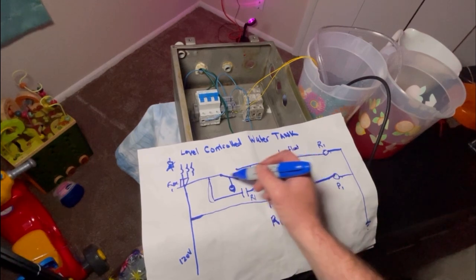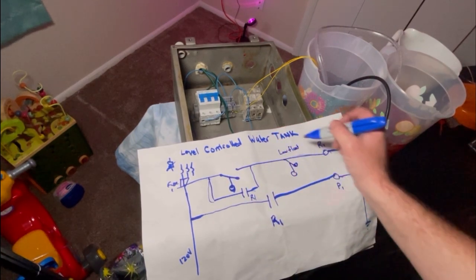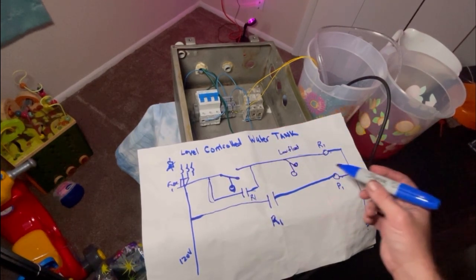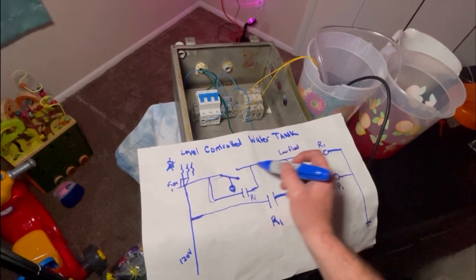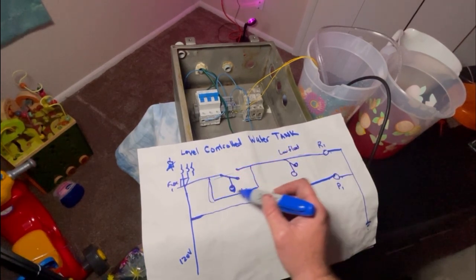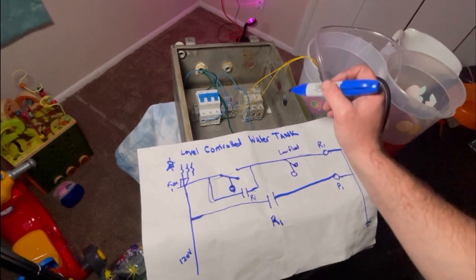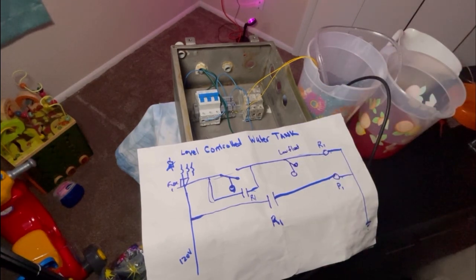So when the high float turns on, this one's going to stay active most of the time because it's near the bottom of the tank. This one's going to turn on. It's going to energize relay 1. We're going to seal in here. And once that low float is hanging, then we're going to interrupt the circuit. That's how I'm going to run this. Let's wire it up. If I made a mistake in my logic, we're about to find out.